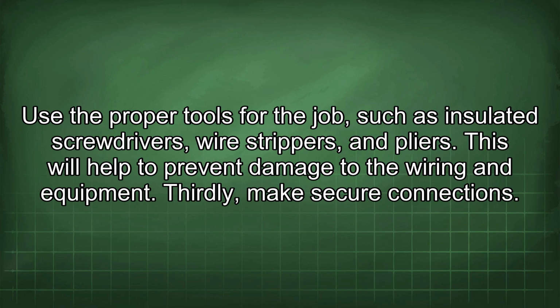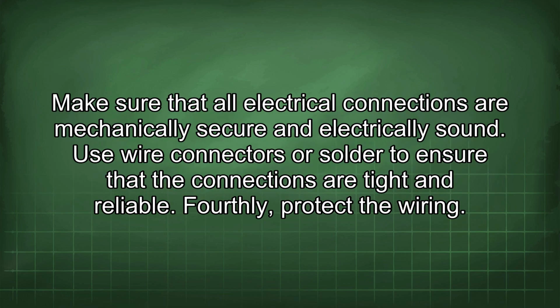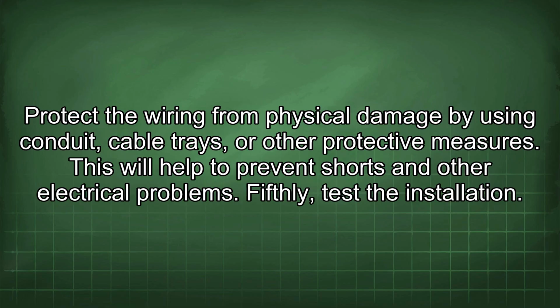Thirdly, make secure connections. Make sure that all electrical connections are mechanically secure and electrically sound. Use wire connectors or solder to ensure that the connections are tight and reliable. Fourthly, protect the wiring. Protect the wiring from physical damage by using conduit, cable trays, or other protective measures. This will help to prevent shorts and other electrical problems.